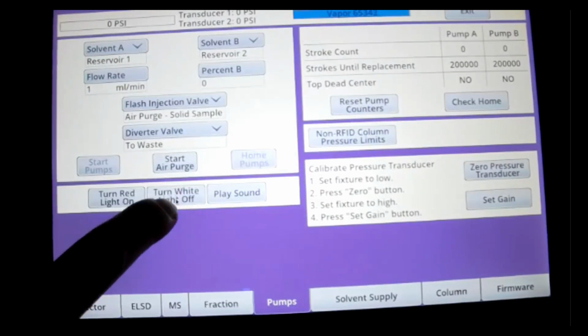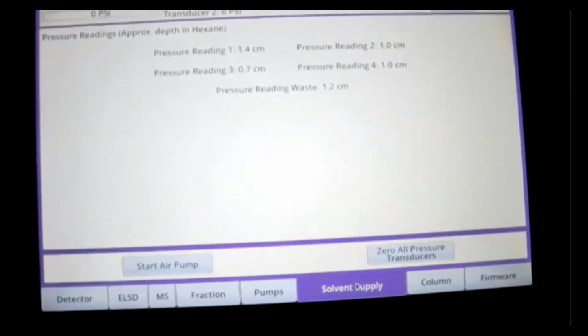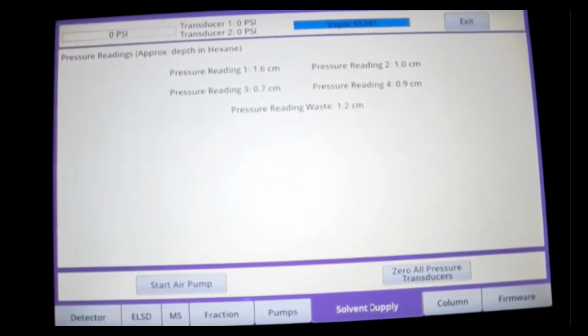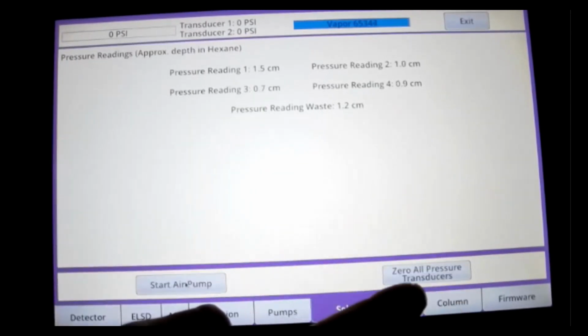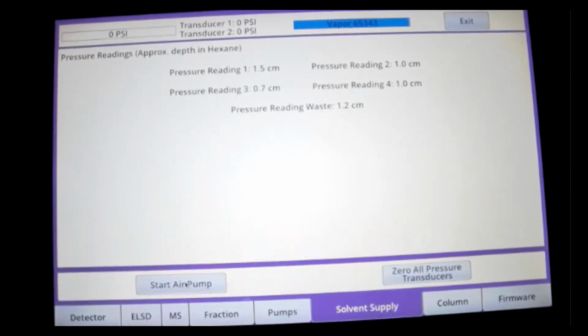You can turn your fancy lights on and off for the unit here. So I've got my red light, my white light. Let's see, there's the red light. You can play your sound. Whoa, that's super cool. All right, now you can go over here to solvent supply if you want. This tells you how much solvent you have in here. You can start your air pump, make sure it's working. You can stop your air pump. You can zero all your pressure transducers, but I would only do that if you remove all your solvent sense lines first from the back of the unit.